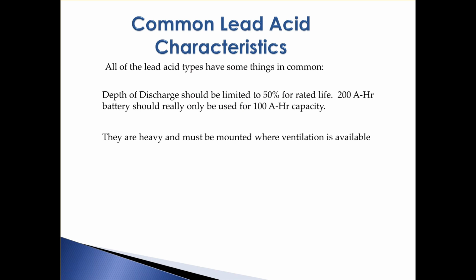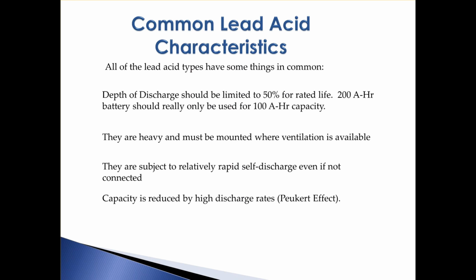Lead acid batteries are heavy and have to be mounted where ventilation is available, and that includes AGM and gel cells as well. They're subject to relatively rapid self-discharge, even when not connected to anything. Capacity is also reduced by high discharge rates, called the Peukert effect, which we'll talk about in a minute. Charge and discharge curves both have significant slope, which gives them an interesting characteristic when used in the real world.